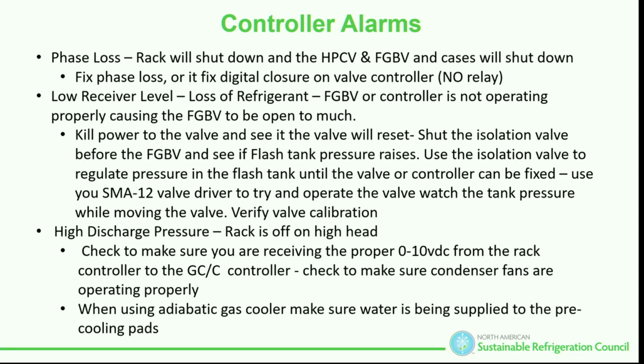If you're kicking off on high head, check your pad, but also look at the coils. If nothing else is going on, make sure I have water if I'm using adiabatic. I have a Güntner that's going to pulse water. If I have a BAC, I've got to make sure the pump is running and the tubes feeding it aren't clogged.